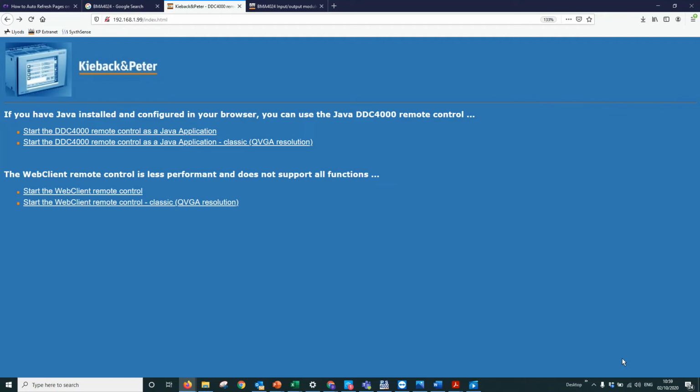If you don't know the IP address, you're going to have to find that out. There are a couple of ways of doing that. You can access the controller if you know the pin number of the outstation for the user level 3, or you can scan the device using a BACnet scanner, and a part of the device object will tell you the IP address. That's a nice little one to get a quick head start on understanding the IP address of the controller.